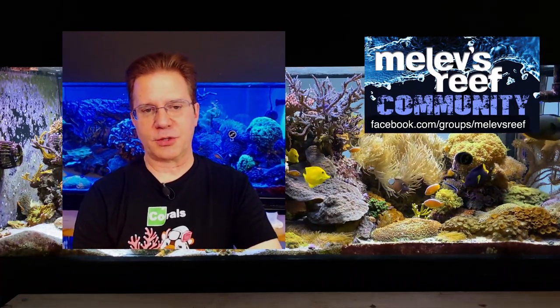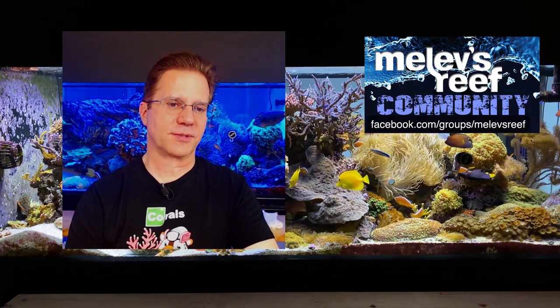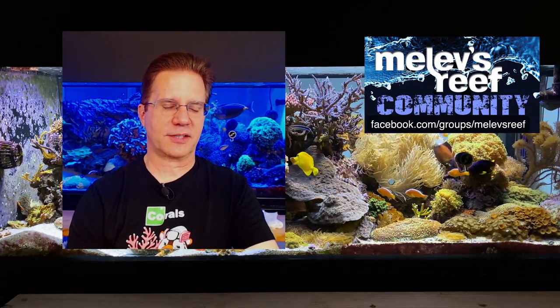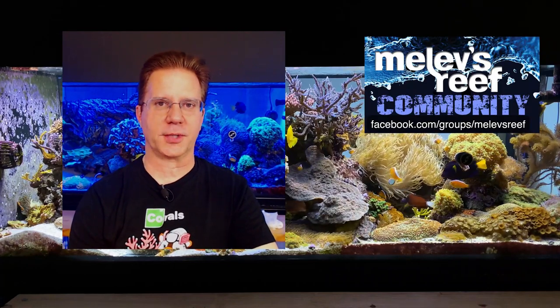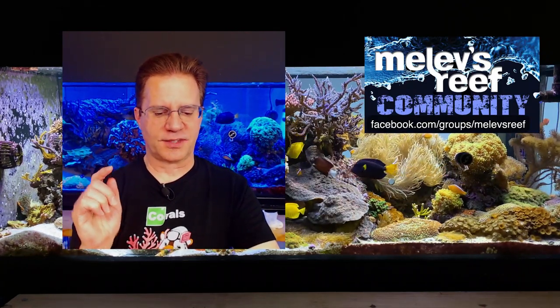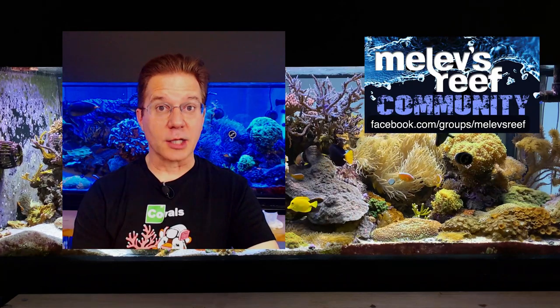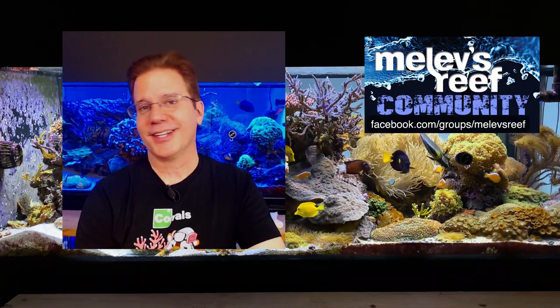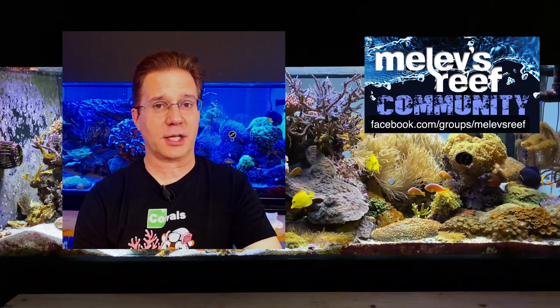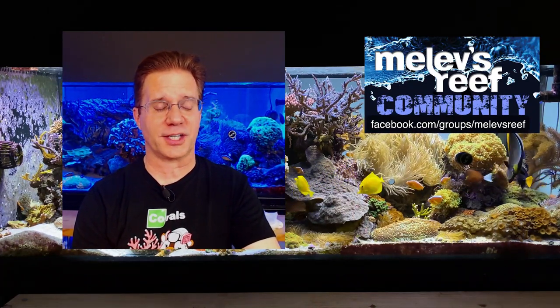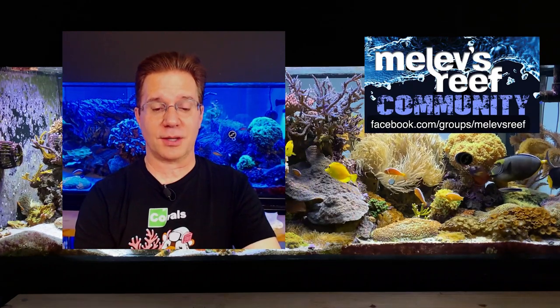A lot of you use dosing pumps, so I always recommend you double check your dosing pumps every single week. Hit the test button if you need to. Calibrate them once in a blue moon. I don't know that you calibrate them more than once a year, but you probably should be calibrating them every 2 or 3 months to verify that the number coming out is the number you're programming.